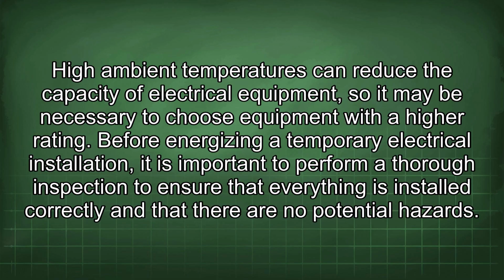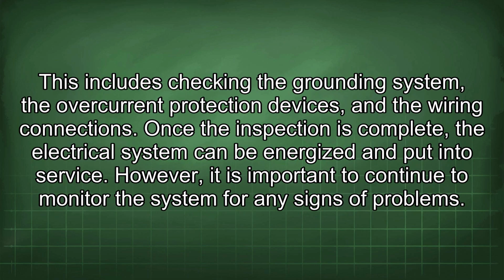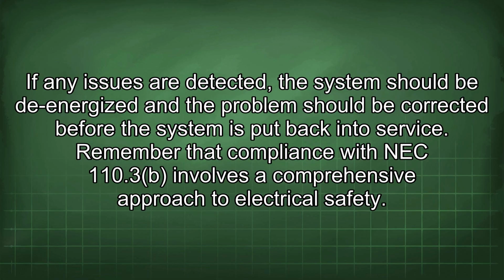Before energizing a temporary electrical installation, it is important to perform a thorough inspection to ensure that everything is installed correctly and that there are no potential hazards. This includes checking the grounding system, the overcurrent protection devices, and the wiring connections. Once the inspection is complete, the electrical system can be energized and put into service. However, it is important to continue to monitor the system for any signs of problems. If any issues are detected, the system should be de-energized and the problem should be corrected before the system is put back into service.